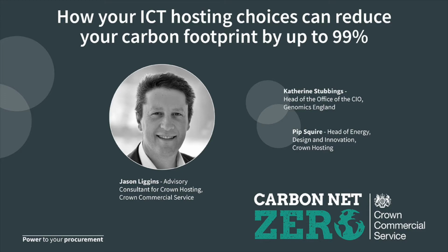So to try and illustrate this, a small NHS trust may have an average data center load of 50 kilowatts. That might be 1 or 2 high density racks, or maybe 5 10-kilowatt racks. But over a year, this would consume the same amount of electricity as 100 average homes. And it would emit, assuming a normal electricity supply from the grid, i.e. not a special deal for renewable energy, some 80 tons of CO2 equivalent. If you scale that up to a large government department with a data load of about 4 megawatts, that's 4,000 kilowatts, this would consume the same amount of electricity as 9,000 homes or a market town, and it would emit some 6,400 tons of CO2. So if you move to a sustainable, energy-efficient data center running on renewable energy, you'd clearly have a significant reduction in CO2 emissions, and therefore you could play a really strong contributing role in achieving a government target of net zero by 2050.